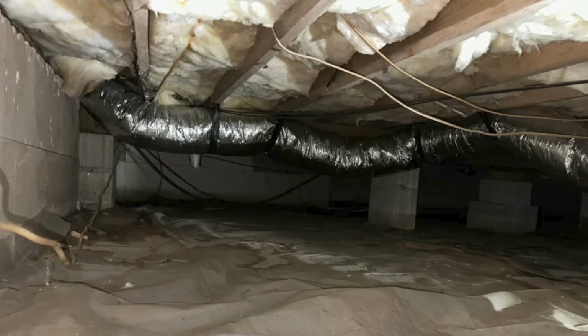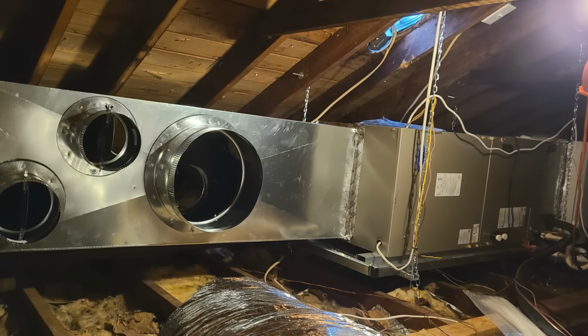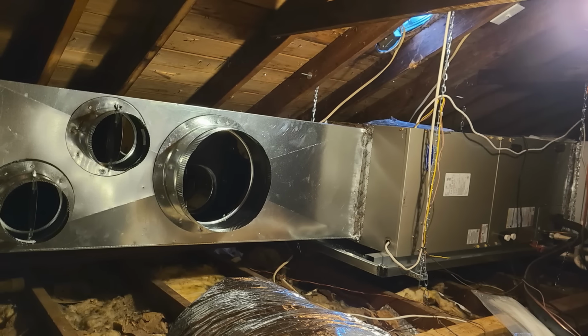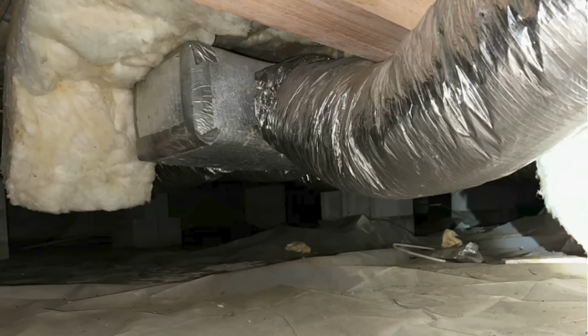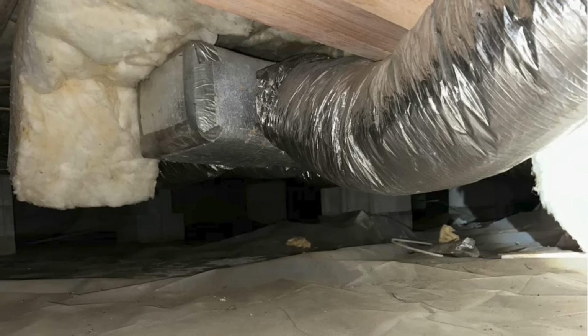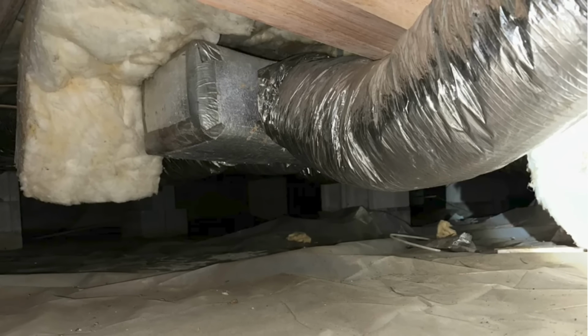We make these summertime condensation problems so much worse when we locate our air conditioning ductwork and air handling units outside of the conditioned space, like in vented attics or vented crawl spaces, where that hot, humid air can easily come into contact with that cold ductwork.